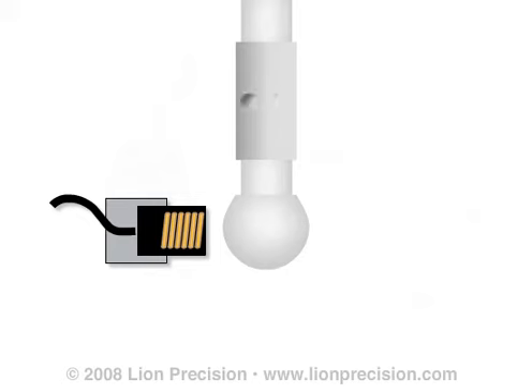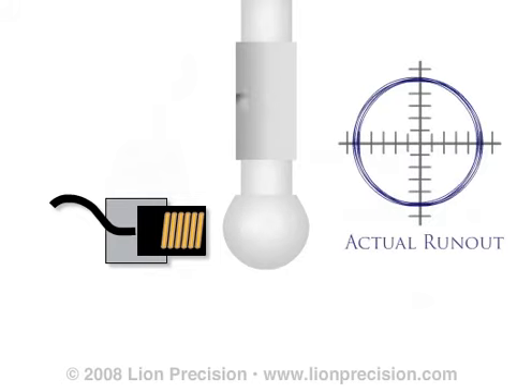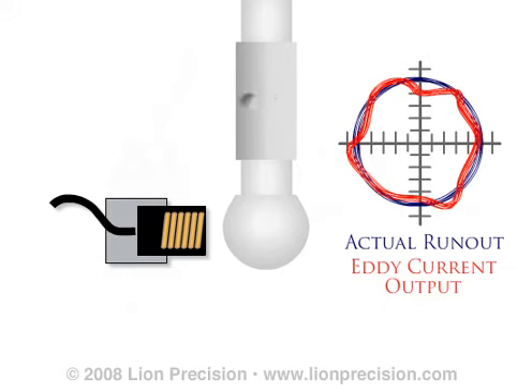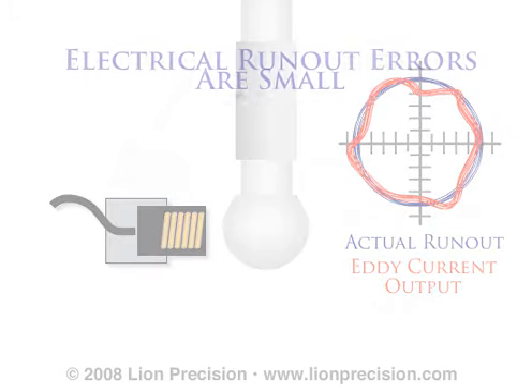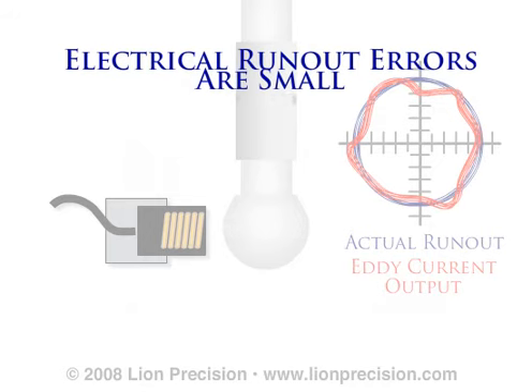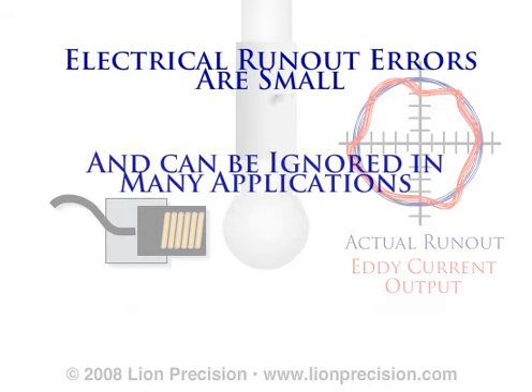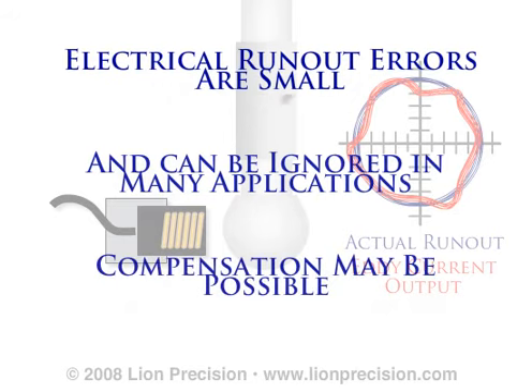An eddy current sensor can be mounted to measure the runout of a rotating shaft. But even if the shaft is ideal, with absolutely no runout, a high-resolution eddy current sensor will detect a repeatable pattern of changes as the shaft rotates. These changes are a result of small variations in the material. This phenomenon is well known and is called electrical runout. These errors can be very small, in the micron range. Many shaft runout applications, especially those in hostile environments where eddy current sensors are the norm, are looking for much larger errors and can therefore tolerate these errors.